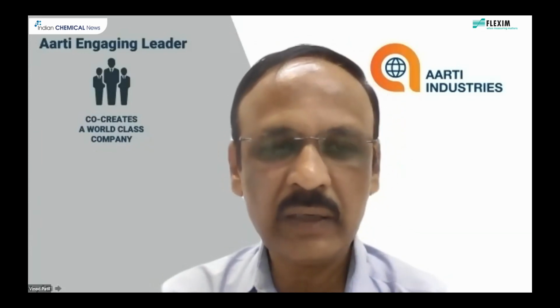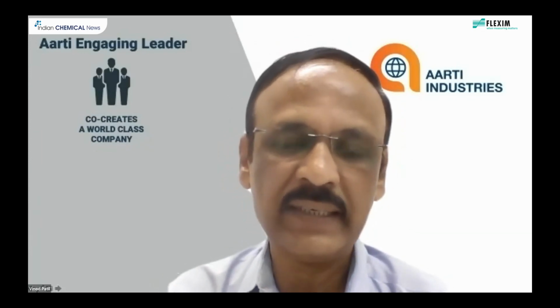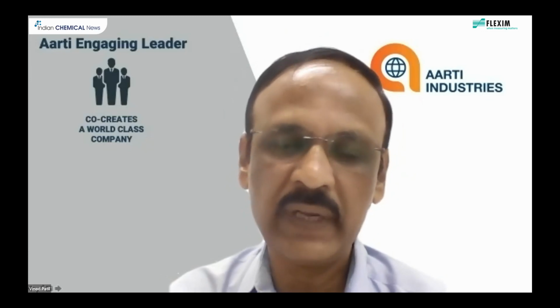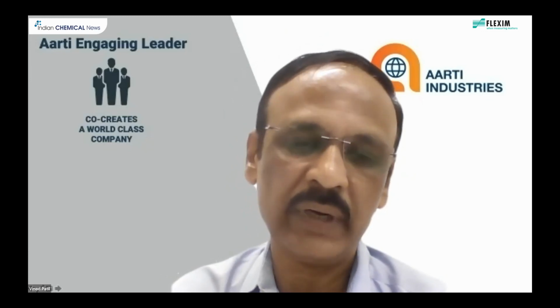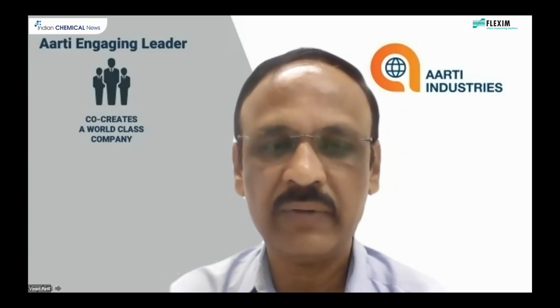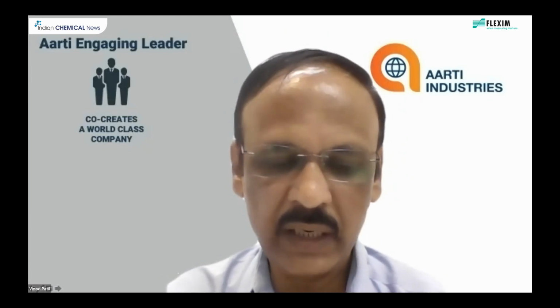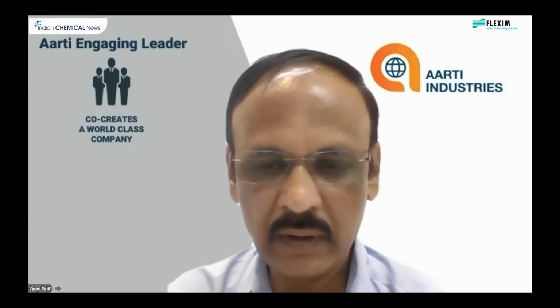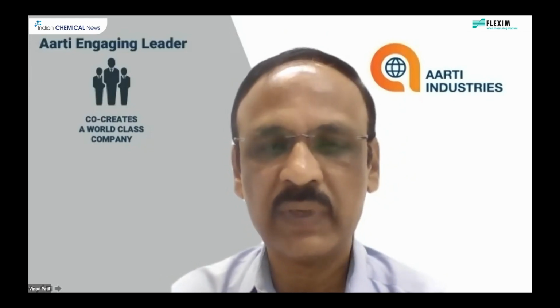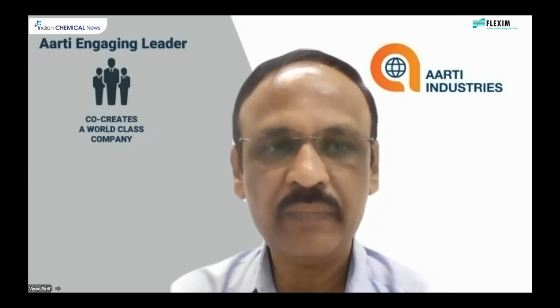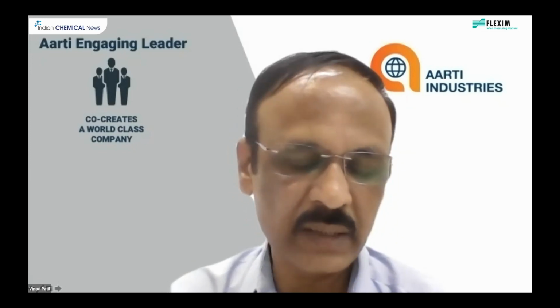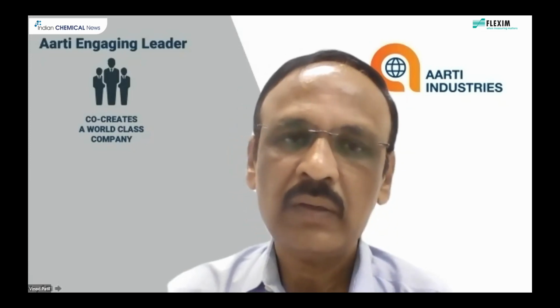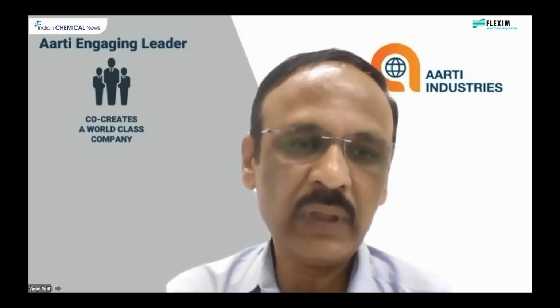We have a total of two installations. One is for the inline, where we replaced the inline with the non-contact type. That is for the concentrated SO3. Here we were facing problems of accuracy as well as maintenance. So there were a lot of challenges, and we overcame all of them with the non-contact type. Post installation, as such, there is no issue, and measurement accuracy is also maintained. So we have come out of all the worries.